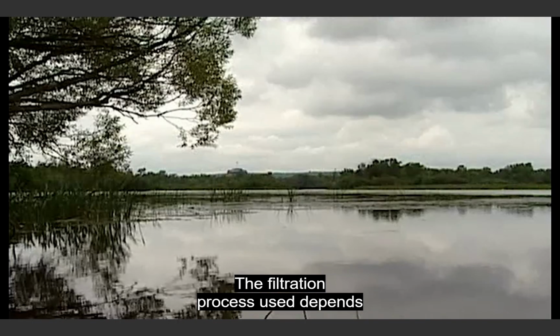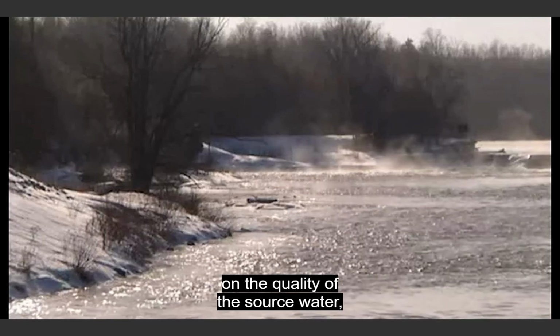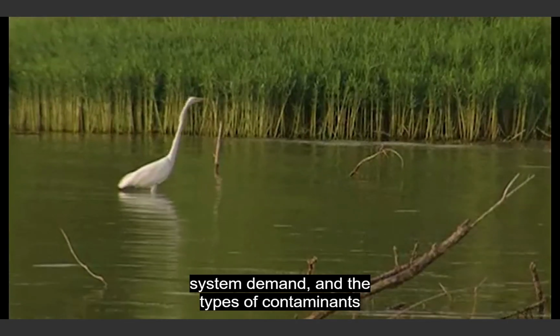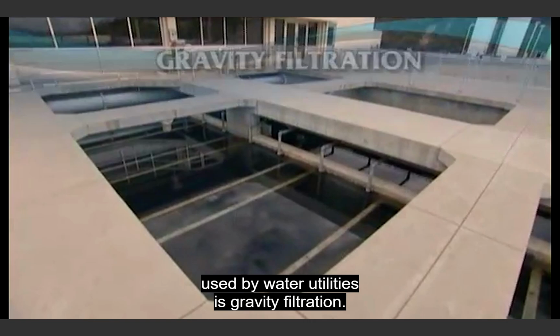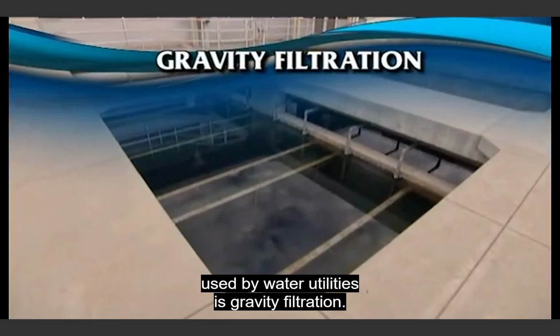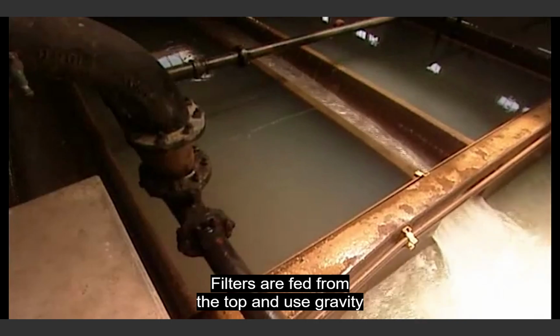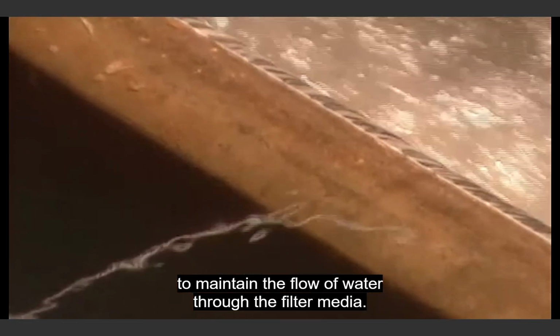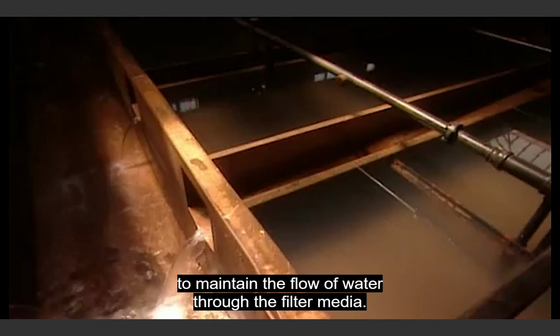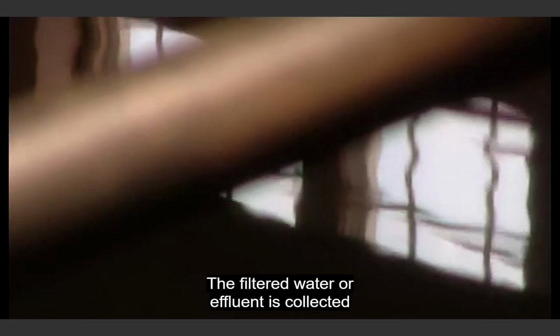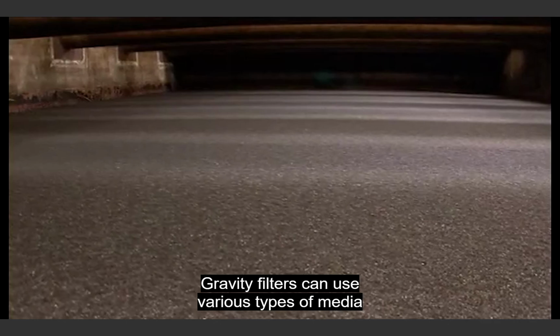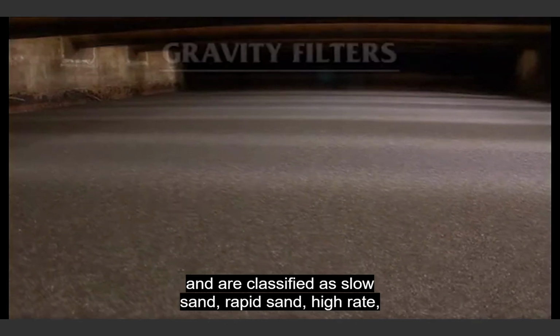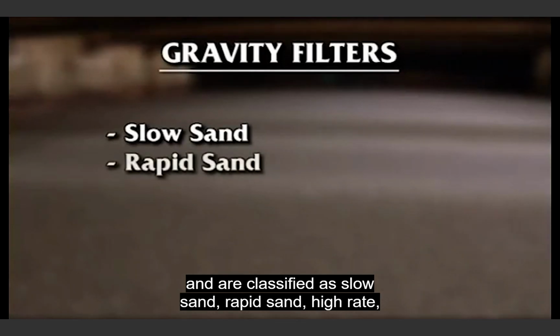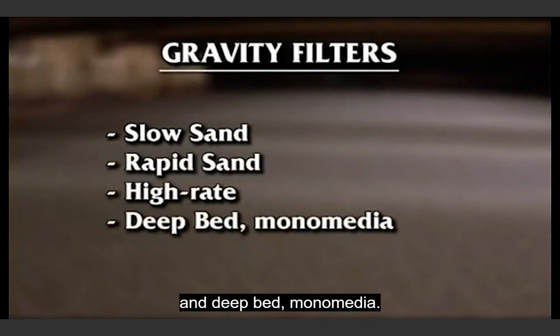The filtration process used depends on the quality of the source water, system demand, and the types of contaminants that need to be removed. The most common method of filtration used by water utilities is gravity filtration. Filters are fed from the top and use gravity to maintain the flow of water through the filter media. The filtered water, or effluent, is collected at the bottom of the filter. Gravity filters can use various types of media and are classified as slow sand, rapid sand, high rate, and deep bed monomedia.